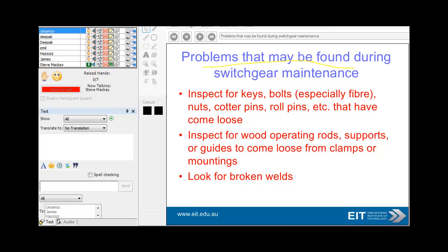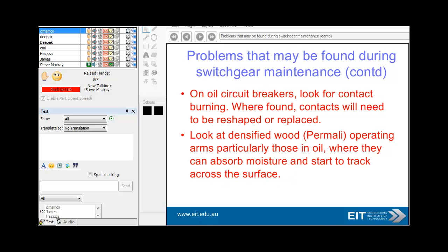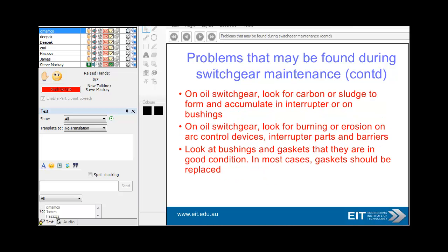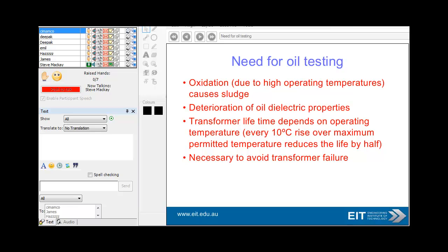Problems that may be found during switchgear maintenance include inspecting for damaged keys and bolts, worn or damaged operating rods, supports, and broken welds. If you find worn contacts, you need to reshape or replace them. Moisture on wooden operating rods can cause tracking across the surface — it's quite an onerous but very critical process. With oil switchgear, you will inevitably see carbon or sludge — check for that, along with burning erosion. Make sure bushings and gaskets are always in good condition, replacing gaskets as necessary. Oil testing is an art in itself — you need to check for oxidation of the oil and deterioration of dielectric properties.